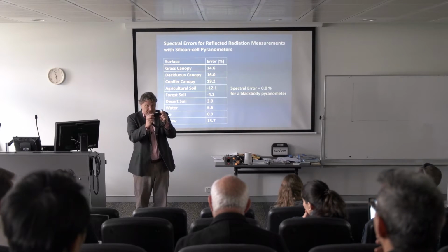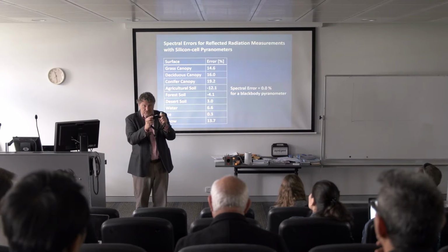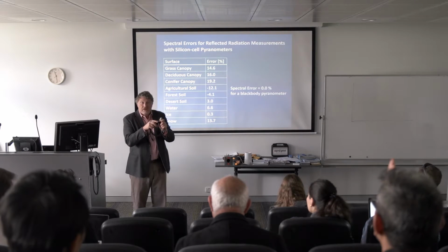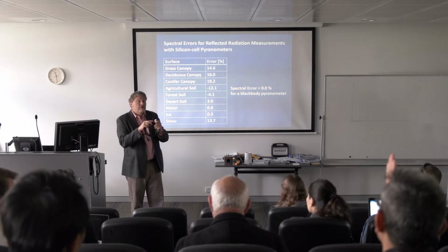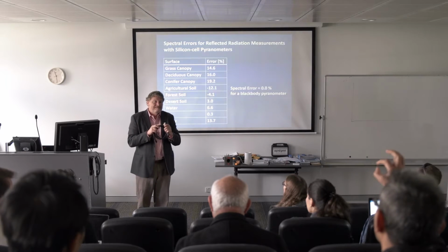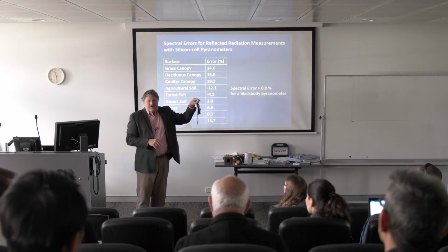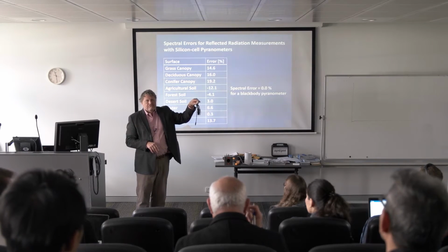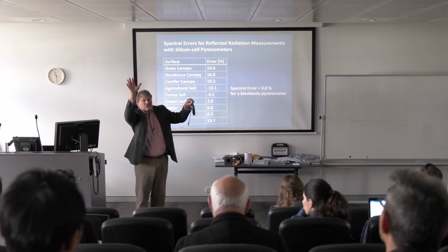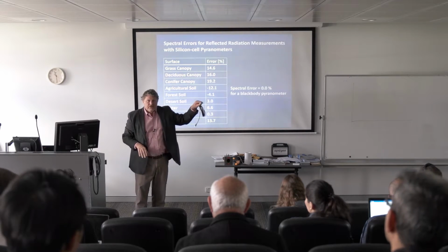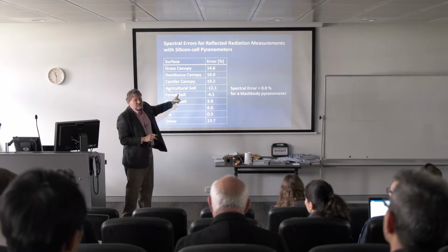They're on a leveling plate, so the standard position is perfectly horizontal. But it would be a big error if you use it vertical, like in a wall. Oh, like this? Yeah, okay. Yes, there is. Same thing, because you're not measuring the sky, it's reflected.